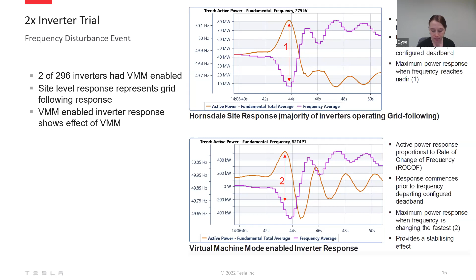Now I'll move on to the most recent milestone, which was undertaking and passing the commissioning or hold point testing at Hornsdale. Hold point testing is aimed to demonstrate that the BESS can comply with the connection agreement, or in this case, the change connection agreement, to prove the accuracy of the model upon which the agreement was based. The commissioning test in this case was conducted in 2 rounds. In the first hold point, the capacity was restricted to 50 megawatts, and in the second hold point, the whole site was enabled with virtual machine mode, and its full 150 megawatt capacity was tested.